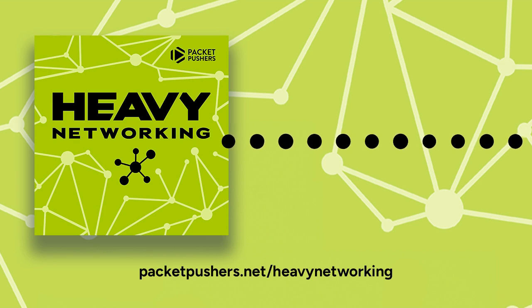They are working on it, for the BACnet IP vendors, they're working on BACnet SC, a newer version of the protocol that turns things upside down. For a BACnet SC device, the OT device out in the field, the IoT device, reaches out and talks to the server on the back end, not the other way around. That's super important and helpful for programming your firewall rules. It also supports DHCP really naturally, it just comes on the network, the out-of-box experience is super easy. It can do DHCP, come on the network, reach out and talk to the backend supervisor or SCADA system, and you're done.